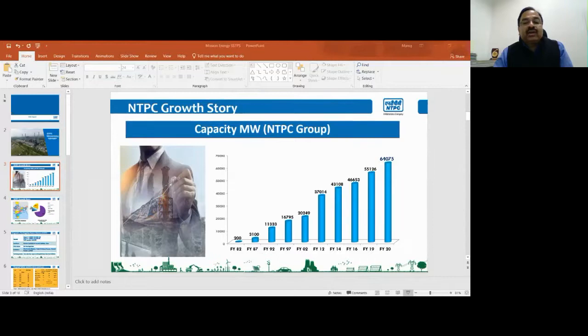Similarly, if we see the turbine efficiency issues, we are maintaining design steam inlet pressure and temperatures, taking up repair and replacement of turbine rotor, turbine blades, and turbine gland packings, and we are also attending to high energy drain valve passings. Similar to the software shown by Mr.